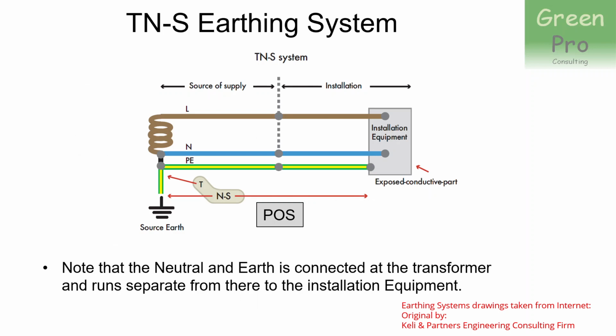So let's just look, what is a TNS system. Let's say I use a transformer in the street. If you have one of the phases, the live goes straight through to the point of supply, right into your house, and the neutral at the transformer is connected to protective earth. From there right into your house there is a neutral and an earth conductor which are kept separate all the way. That is a TNS earthing system, and that is what the inverter will most probably be.